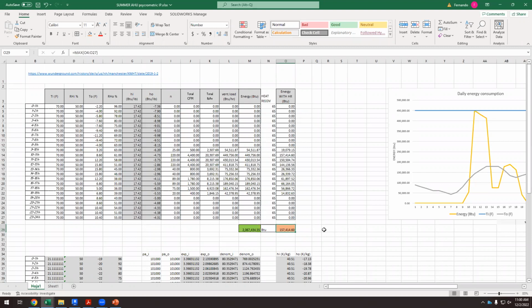What if we have a boiler with 500,000 BTU? So we have a boiler that is far too big. If we need 150, and we have something like that, the boiler will start, and we will reach this power immediately, and then the boiler stops, and then we have to start and stop again, start and stop again.